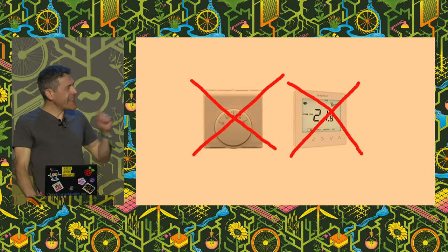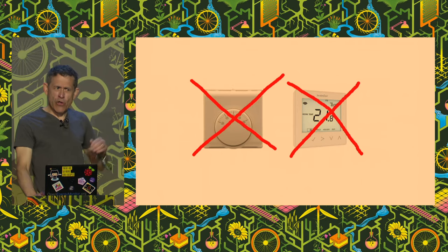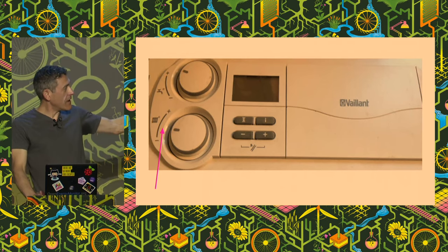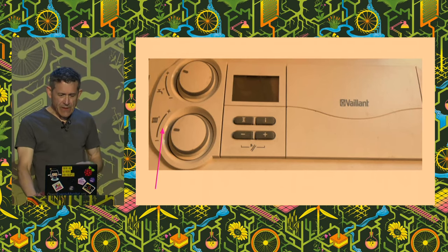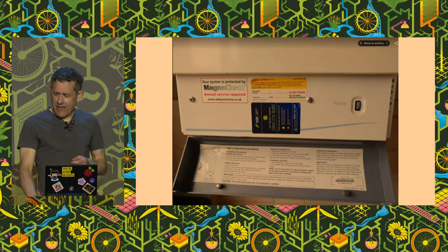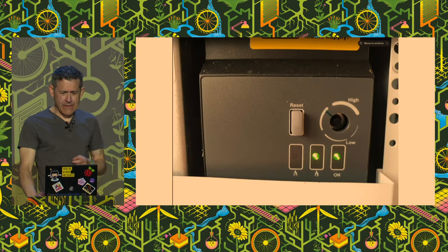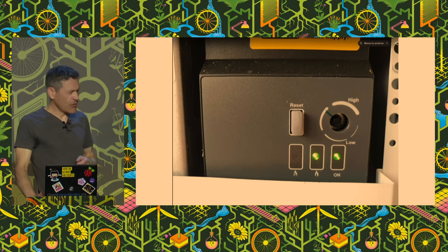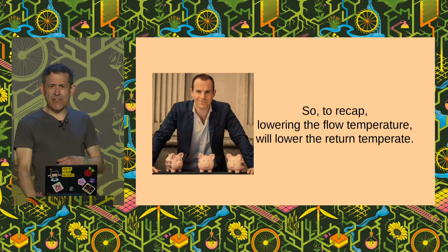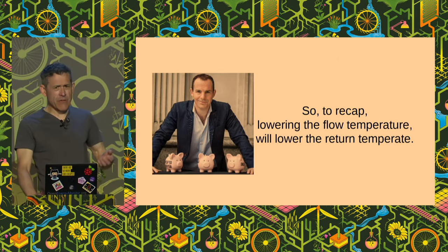The flow temperature control isn't the kind of room thermostats you see on the wall — those just say how hot you want the room. What you need is controls which are actually on the boiler itself, like this one here with the pink arrow. If you're lucky. If you're unlucky like me, you'll need a set of screwdrivers and some spanners and start dismantling your boiler until you find the flow control. To recap: lowering the flow temperature lowers the return temperature, leads to more condensation, which preheats the water, which means you use less gas, which saves you money and also the environment.